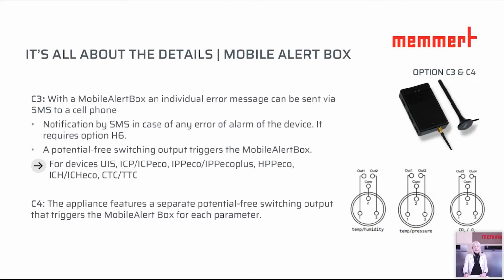Besides this C3, we also have the C4, and here we have the possibility that the alarm will be indicated. So for C3, if you get an alarm on your mobile phone, you will not recognize which alarm has been triggered. You will just see there's an error. If you go for C4, there is an indication of which alarm is going to be triggered. So we have here on the unit separate potential free switching outputs, and this triggers the mobile box for each parameter. For example, we have here the output in regard to temperature and humidity, which refers then to a humidity chamber.